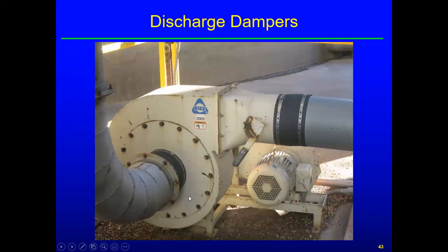Okay, there's another one, a little Kice blower you see out there. And really the big question is, what's the damper position? So I would expect if this handle was perpendicular going straight down, that damper would be shut. That's a common way, unless you have some other indication of interpreting this.